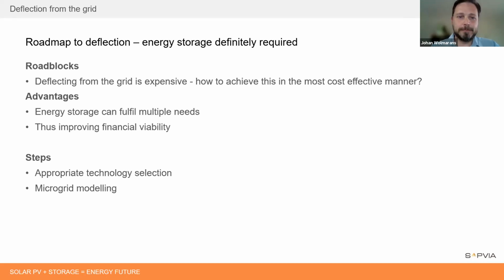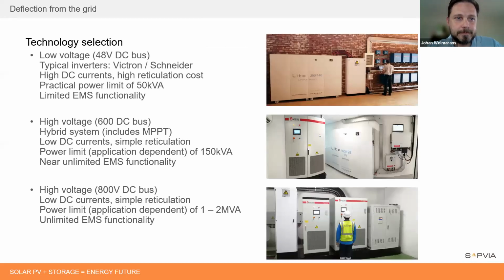From a technology perspective, everyone is familiar with low voltage, more residential type solutions, which is a 48 volt based system. These typically have a limit - you can go as high as 100 kVA in certain instances, but a practical limit is 50 to 60 kVA. This is purely based on your copper and reticulation, which becomes incredibly expensive due to the high currents.